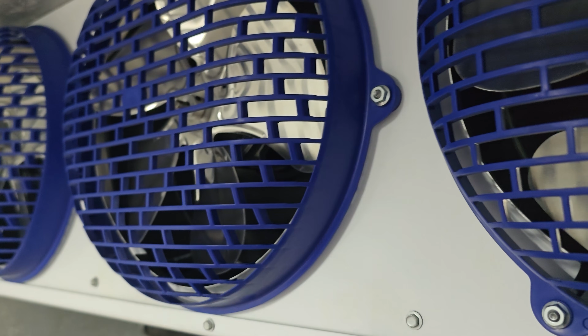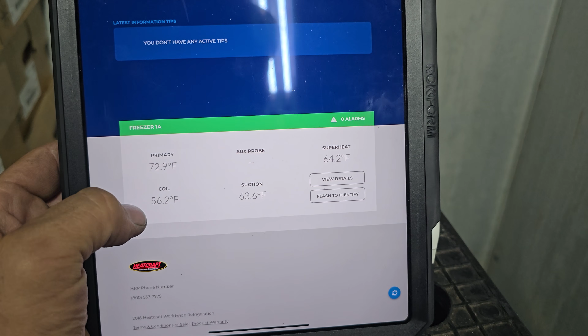So we changed this one. I did verify all the heaters are working. It does smell a little burny in here, but it's just basically all the oils burning off the heat strips. So we're just watching it, and it's literally about to terminate at 60 degree coil temp. It's nowhere near gonna meet the 20-minute time.